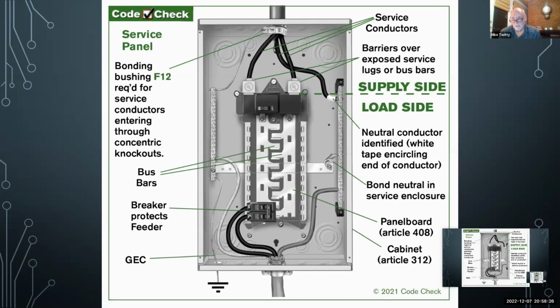You see it done sometimes. Somebody will have a lot of black THWN and they'll pull it in 3 times and they'll tape up one as white, one green, and then the black hot. That's not allowed for smaller conductor wires.